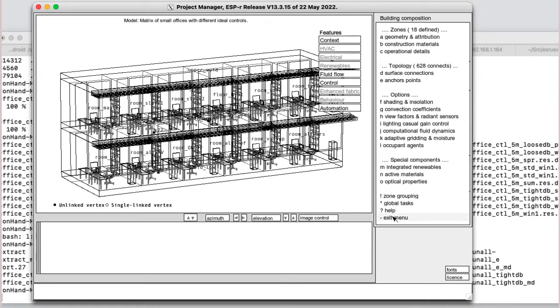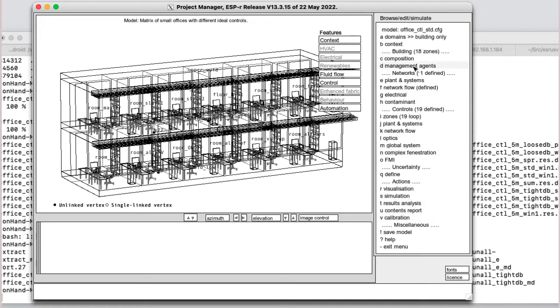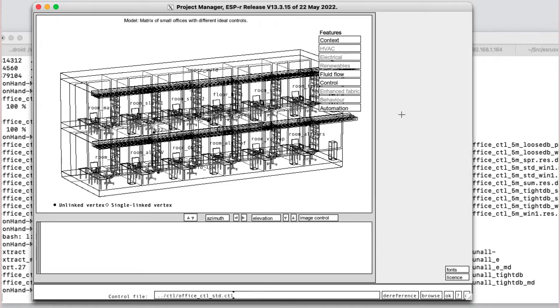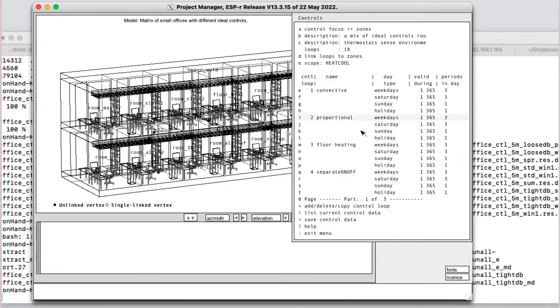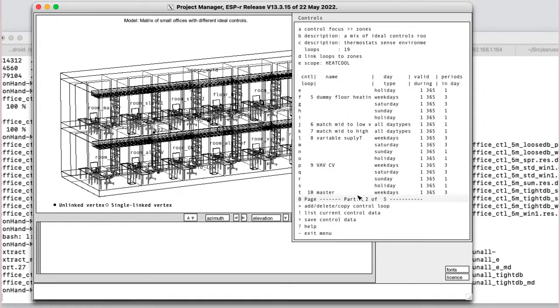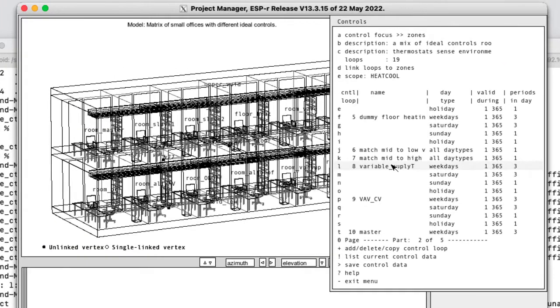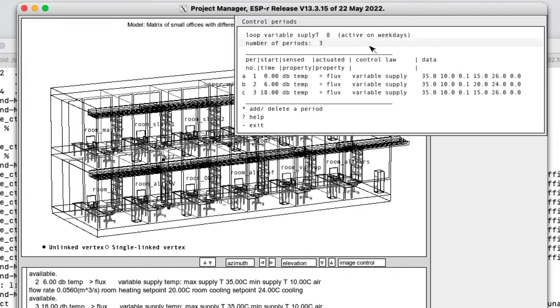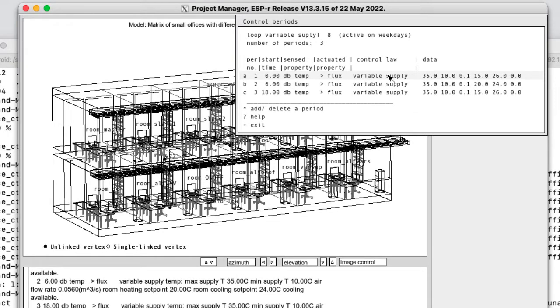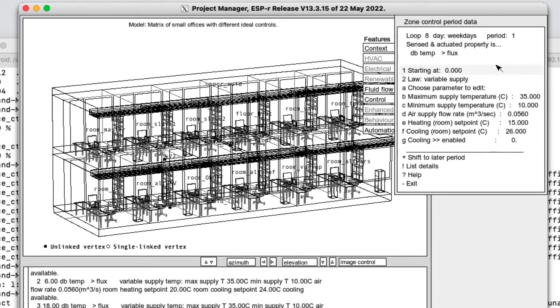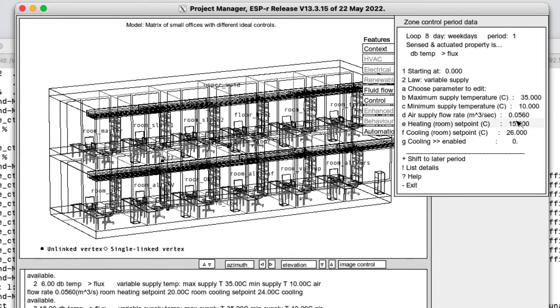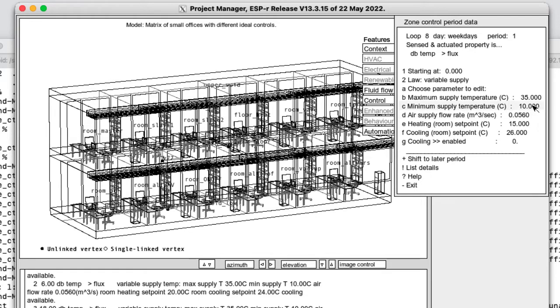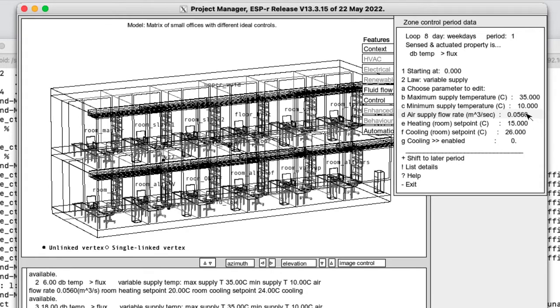If we look in controls, here's one definition of variable supply. And the period data basically sets out the few attributes, which are the heating and cooling setpoint. This is the overnight with maximum supply temperature for heating of 35 degrees, minimum supply temperature for cooling of 10 degrees, and an airflow rate, which is equivalent to five air changes per hour.